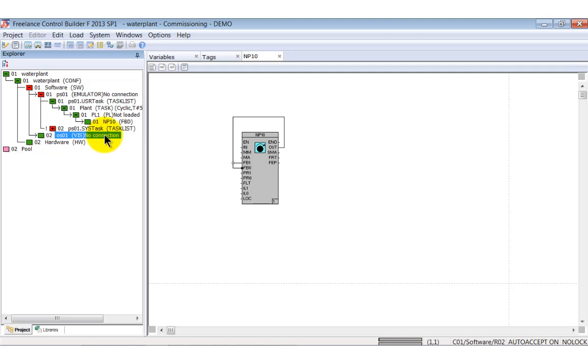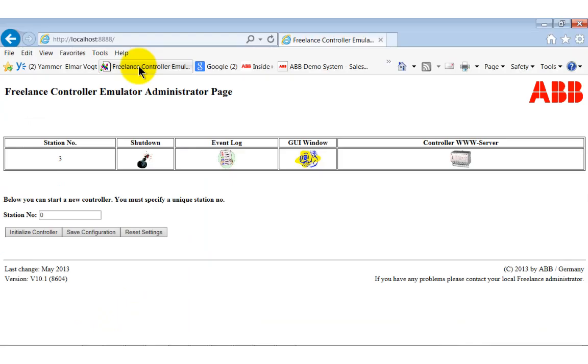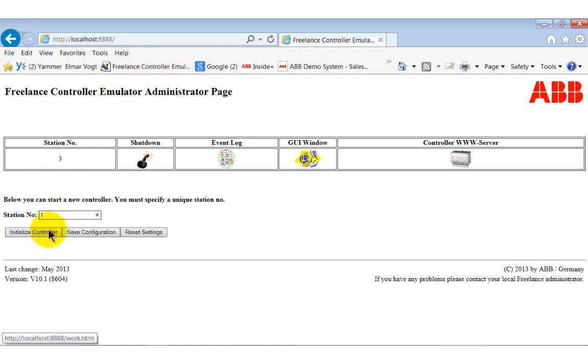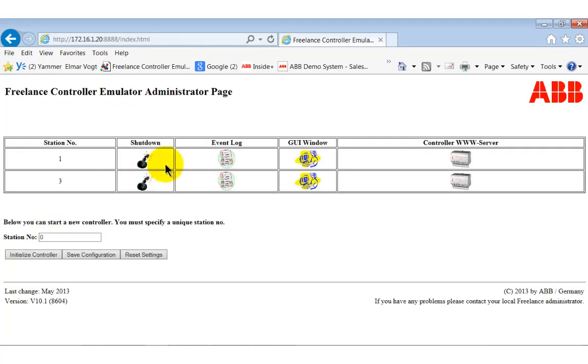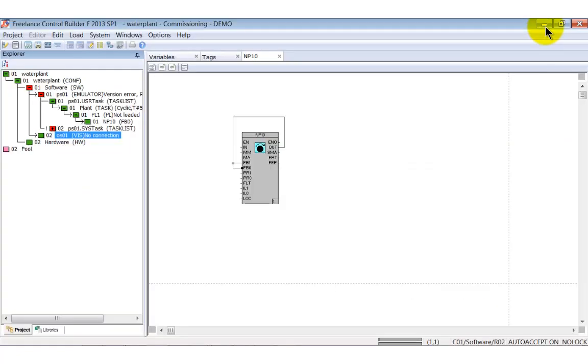Open the Internet Explorer and enter the IP address. It will help a lot if you create a favorite for the emulator page as I did. Click the start controller button so that a new controller with station ID 1 is started. If you take a look at the CBF's commissioning mode, you will see that the process station is now running, but with the wrong version of the program. That's correct as we haven't loaded the program yet.